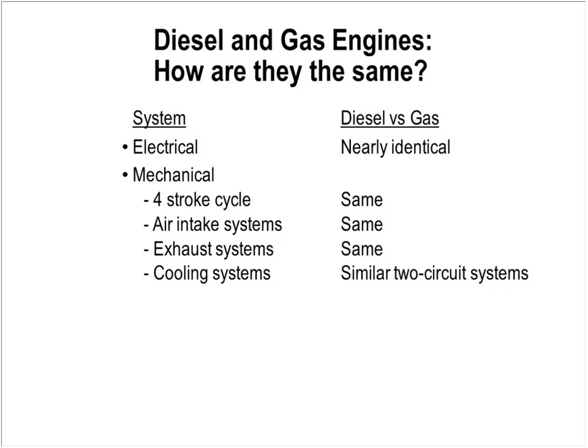As far as the mechanical side goes, both engines are 4-stroke cycle engines. The air intake systems are basically the same in that you're worried about controlling whatever is in that air—contamination from airborne particulates, dust, dirt, whatever. The same considerations you'd use on a diesel engine, you'd use on a gas engine. So if I required dust ejectors or dual filters on a diesel engine, I would require those same types of filters on the gas engine side.